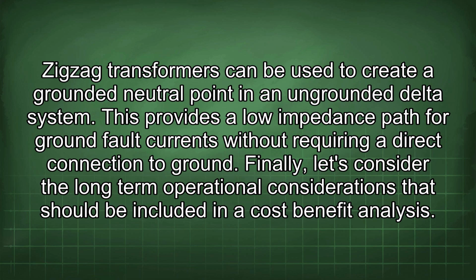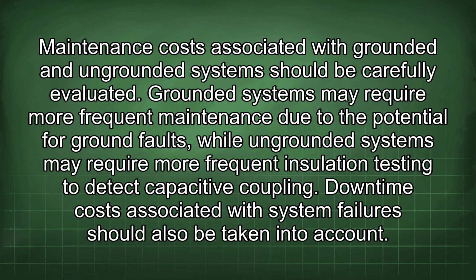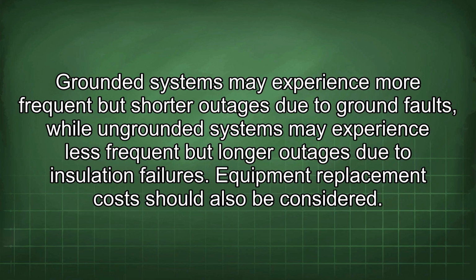Finally, let's consider the long-term operational considerations that should be included in a cost-benefit analysis. Maintenance costs associated with grounded and ungrounded systems should be carefully evaluated. Grounded systems may require more frequent maintenance due to the potential for ground faults, while ungrounded systems may require more frequent insulation testing to detect capacitive coupling. Downtime costs associated with system failure should also be taken into account. Grounded systems may experience more frequent but shorter outages due to ground faults, while ungrounded systems may experience less frequent but longer outages due to insulation failures. Equipment replacement costs should also be considered.